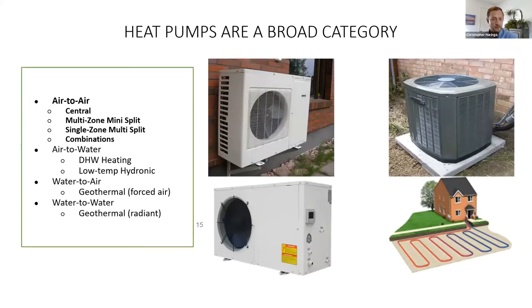So air to water is another of the cool opportunities, using the same technology but transferring heat throughout the home with water. That heat is also taken from the outside air and put into the water, then transferred around the home with hydronic systems using baseboards, radiators, or radiant floor heating. There are a lot of really cool opportunities with new construction, but some challenges on the retrofit side with existing hydronic systems, since the hot water generated by air to water heat pumps isn't as hot as water from traditional boiler systems like oil or gas boilers.